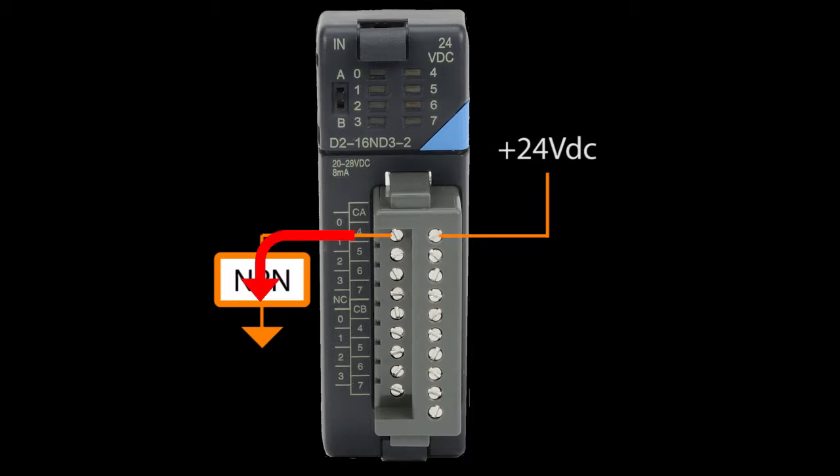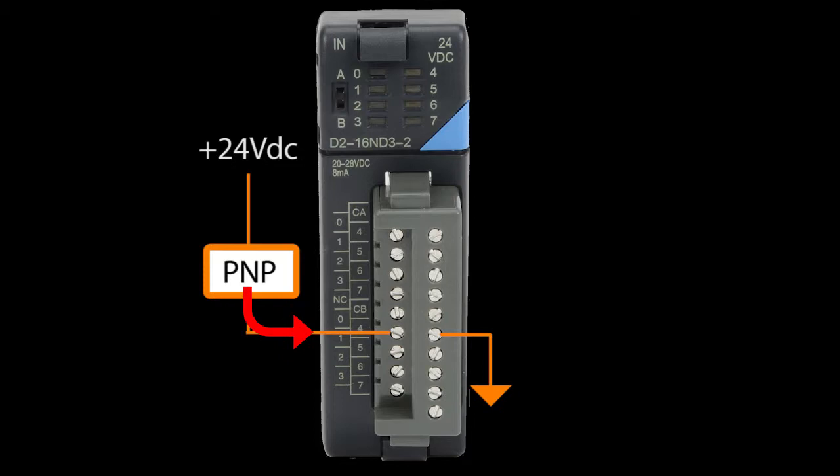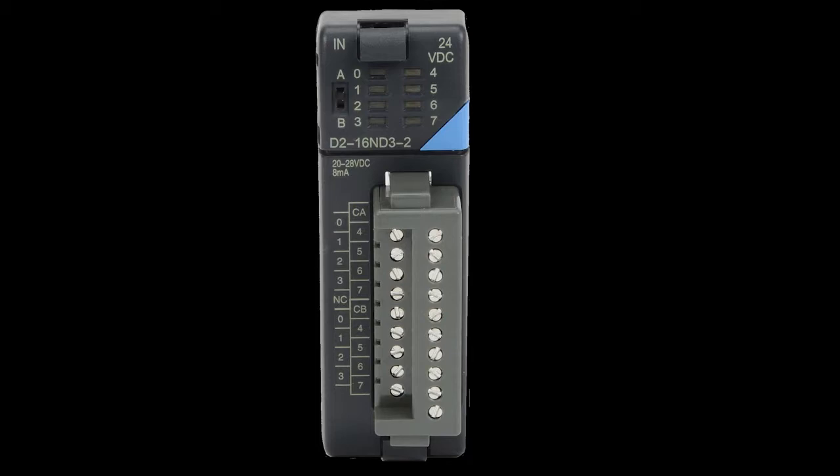And that's really all you need to remember. When you have an NPN sensor which sinks current, you need an input module that can source the current. And when you have a PNP sensor that sources the current, you need an input module that can sink the current. And since this input module handles both, we're in good shape.